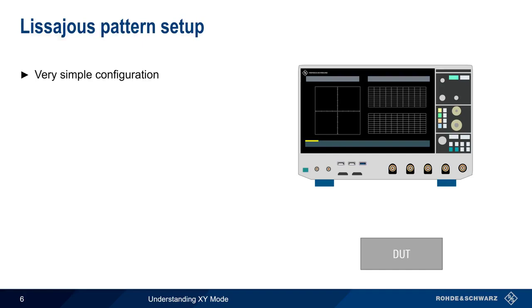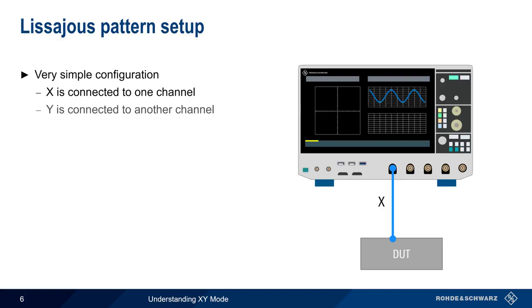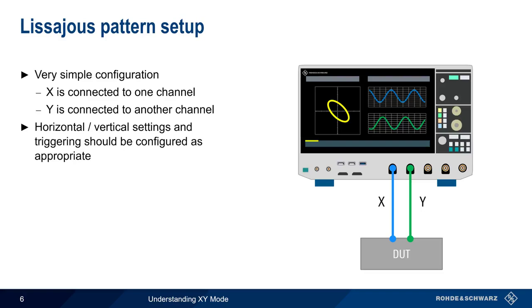Part of the reason why Lissajous patterns are a popular XY mode application is that they are very easy to configure. The X signal is connected to one channel and the Y signal is connected to another channel — often channel 1 and channel 2, though this is configurable on some oscilloscopes. The result will be a plot of X versus Y. Note that like all other scope measurements, the horizontal and vertical settings should be configured appropriately, and a suitable trigger type and trigger parameters should also be set.